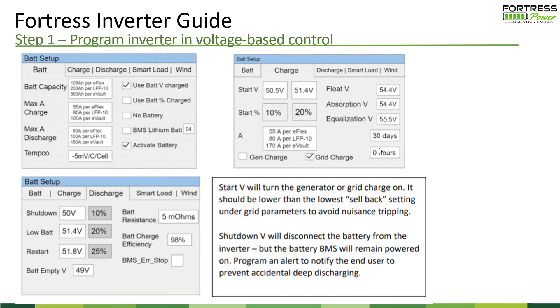These are more suggestions than ironclad voltage parameters. Advanced installers may play around with their alarm level or shutdown voltage to get a broader range out of the battery, or to turn the alert on in a meaningful way. Once the voltage open-source limitations for voltage-based controls go away, you'll be operating the battery off percent state of charge, but this gets you up and running while you make the battery communication cable.